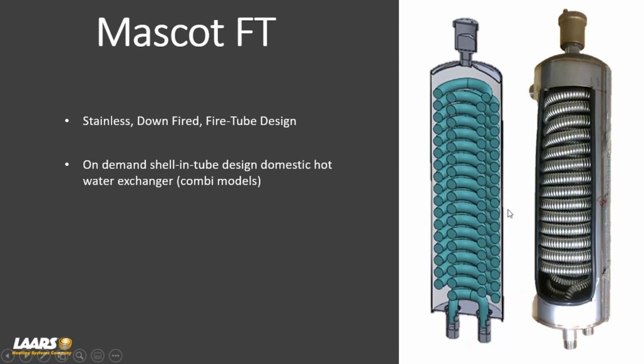Now, most people are familiar with an indirect tank where you have a vessel that holds potable water, and you'll take hydronic boiler water, example of that is 180 degrees, and send that through the coil, and then you're heating the potable water. This is a shell and tube design. What we have here is the vessel itself stores hydronic water. The domestic water travels through this double row of tubes. And this is a 3/4 inch corrugated tube. And again, there's a double row.